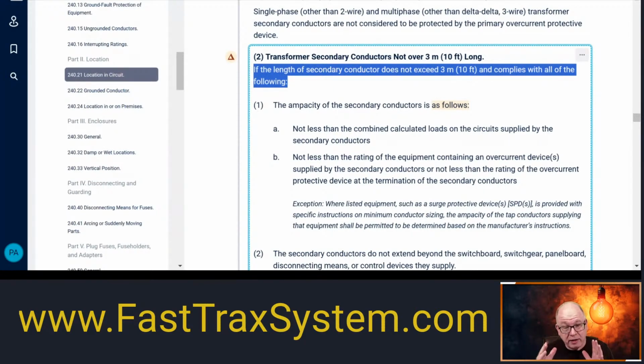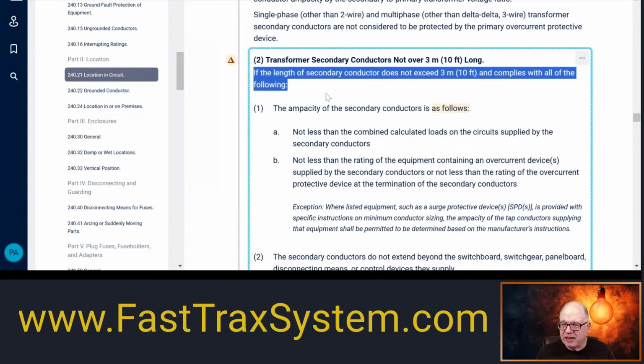This secondary conductor rule is basically saying, similar to the tap, you're connecting to a transformer secondary, and there's a possibility that it could be smaller than what the transformer's output is. Of course, it could be equal to the output, and it could be larger than the output. You can have larger conductors than you need if you want. You've just got to be careful that they can fit in the lugs. But what we do know in this case is, from that transformer, I can go up to 10 feet and determine the size of those conductors based on this allowance here. So 240.21(C), and I'll show you.